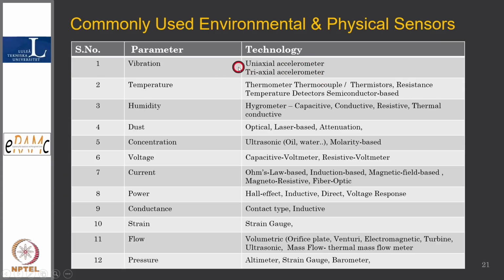And there are sensors put on the sensor assembly. For temperature, we know there are thermometers, thermocouples, thermistors, resistance temperature detectors, and semiconductor based devices - these are the technologies, and which technology suits depends on linearity. For my measurement domain of interest, I should have that area where things are linear, proportional increase or proportional reduction.